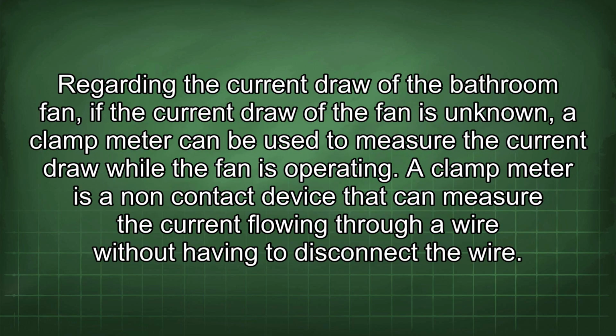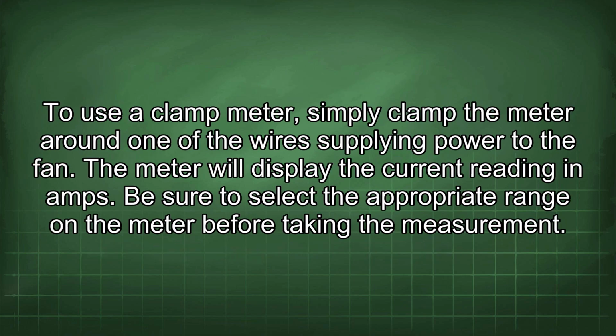Regarding the current draw of the bathroom fan, if the current draw of the fan is unknown, a clamp meter can be used to measure the current draw while the fan is operating. A clamp meter is a non-contact device that can measure the current flowing through a wire without having to disconnect the wire. To use a clamp meter, simply clamp the meter around one of the wires supplying power to the fan. The meter will display the current reading in amps. Be sure to select the appropriate range on the meter before taking the measurement.